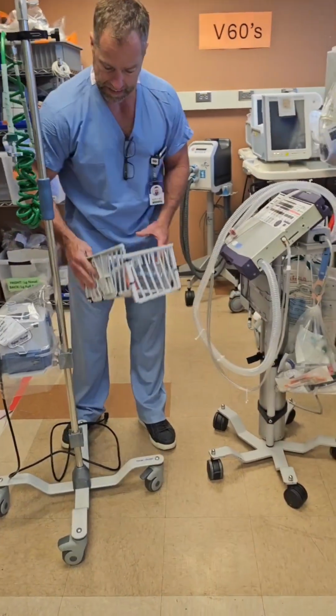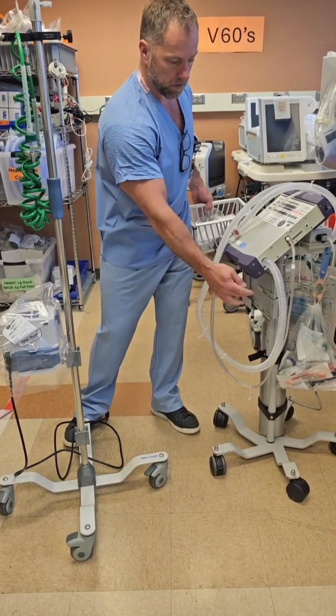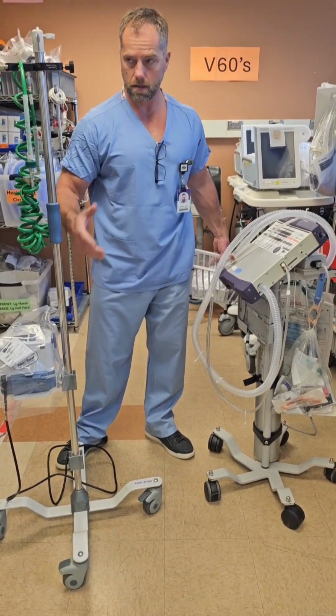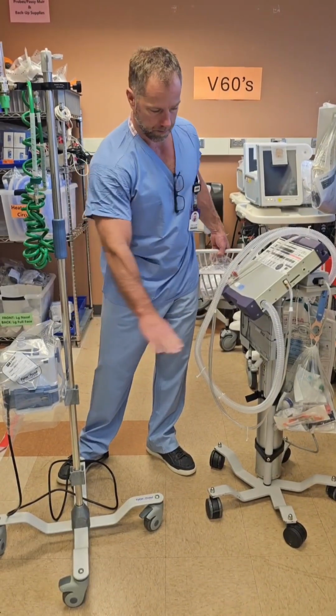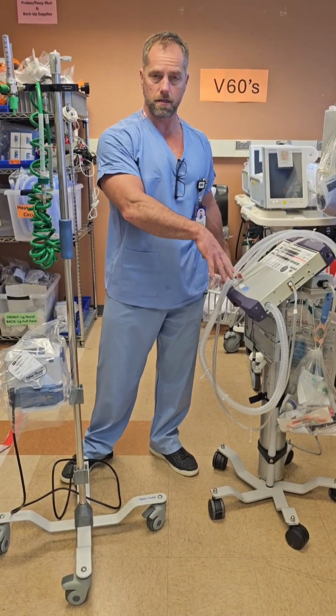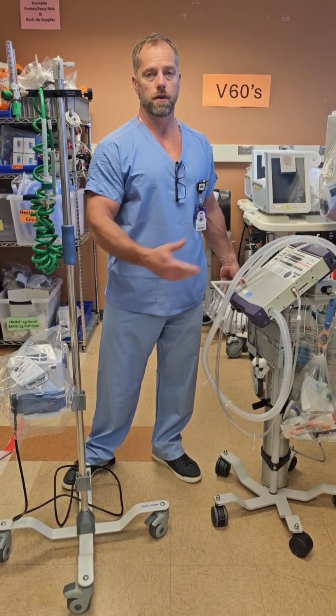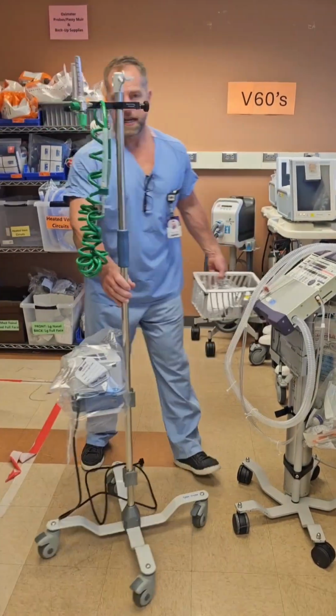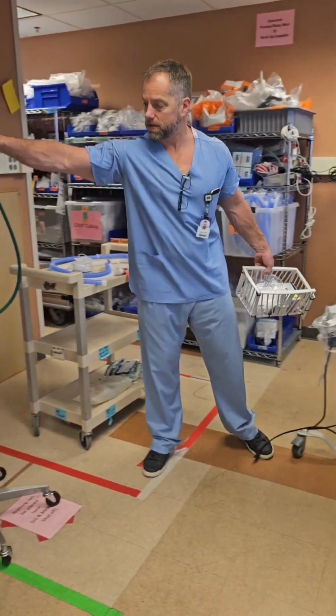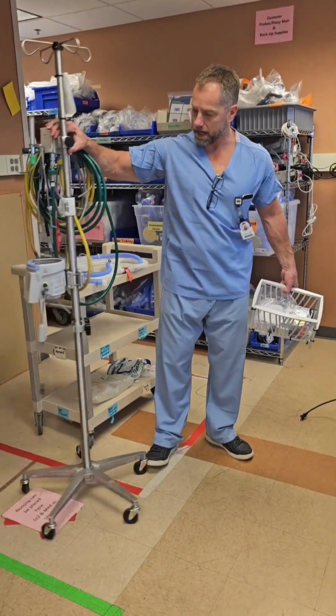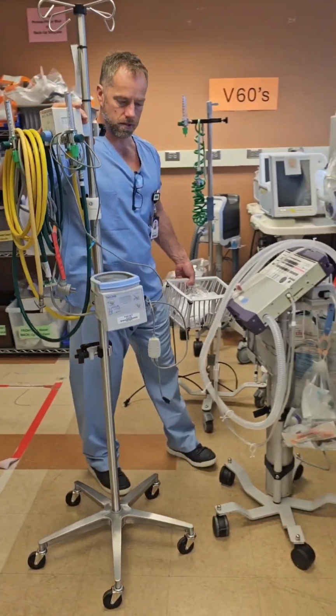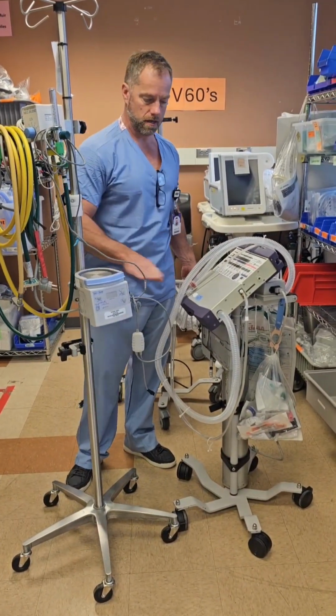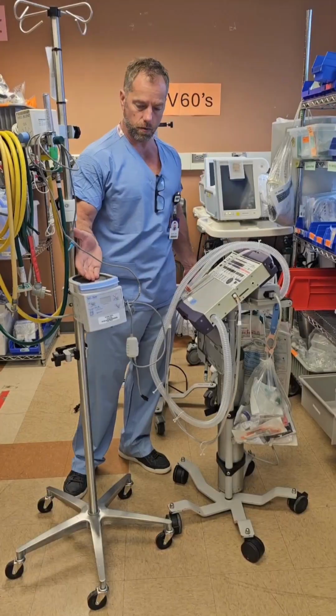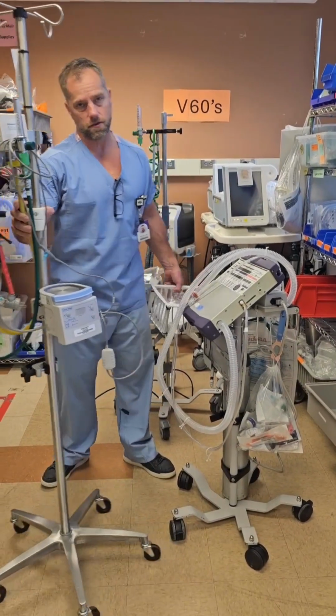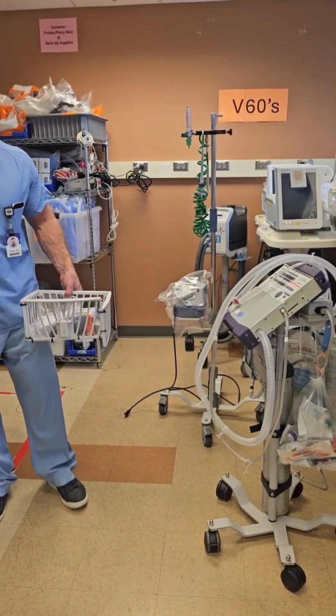Where this basket sits right here is below the ventilator circuit. We want that for our water chamber to be below the ventilator so we're not dumping water into the ventilator accidentally. Also, we don't want to dump water into our patient. In contrast, just for an example, we have this double CPAP pole that we use where the heater pot is higher than the ventilator, and now we have run the risk of dumping water into the vent or the patient, so we don't want to use that.